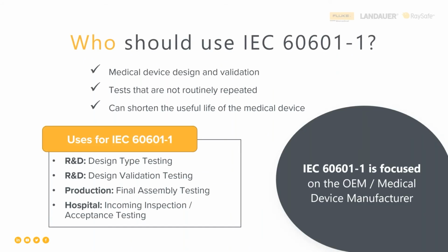All right, so who should use the IEC 60601-1? I've already told you, it's written for the medical device manufacturer in their design validation testing and their final assembly testing in the factory. This one can be used by hospitals for acceptance testing. However, 62353 is also sufficient, and we'll talk about that in a minute.